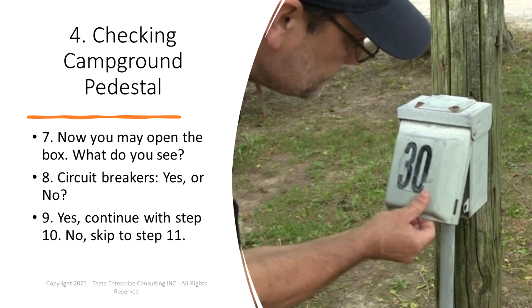For step 10, look at the breakers inside. Are they all off? If yes, while not touching the outside case door, turn them all on and do the test from step 3 again, using the NCVT to touch all around the box, listening for the beep denoting any stray electricity. Be sure to touch the cover also. Once done, if you got no beeping, turn off all the breakers and go to step 12.